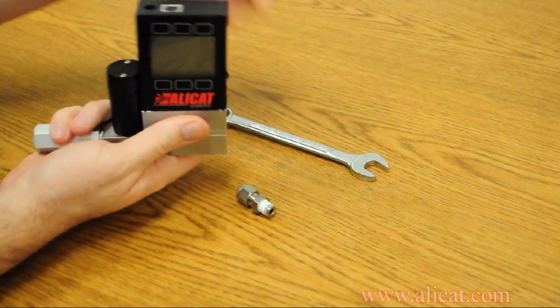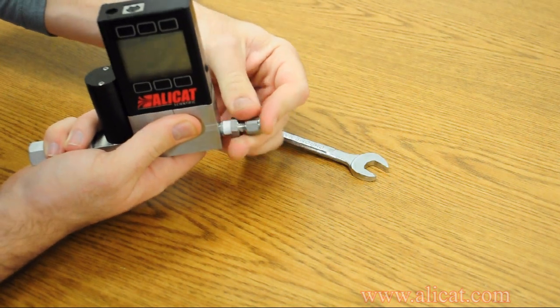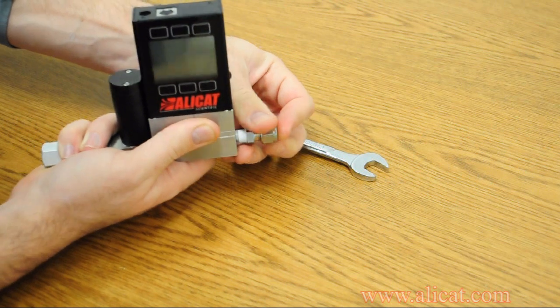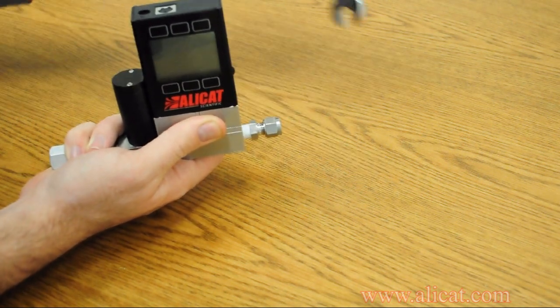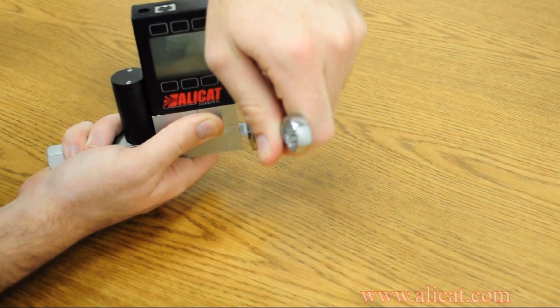When installing a fitting into a port without a valve assembly, you can grip the instrument in one hand while tightening the fitting. Again, avoid using the valve assembly for a leverage point as damage may occur.